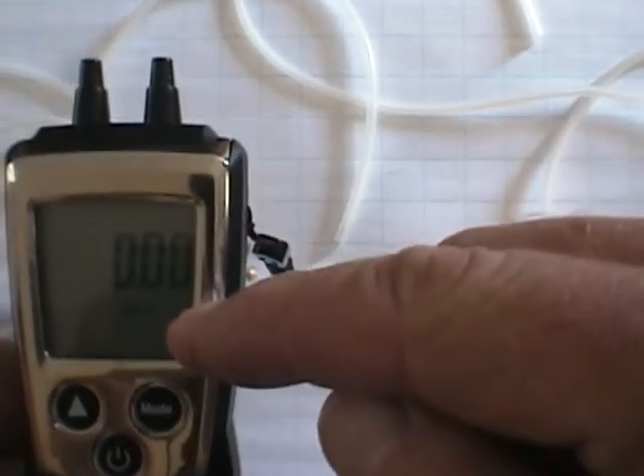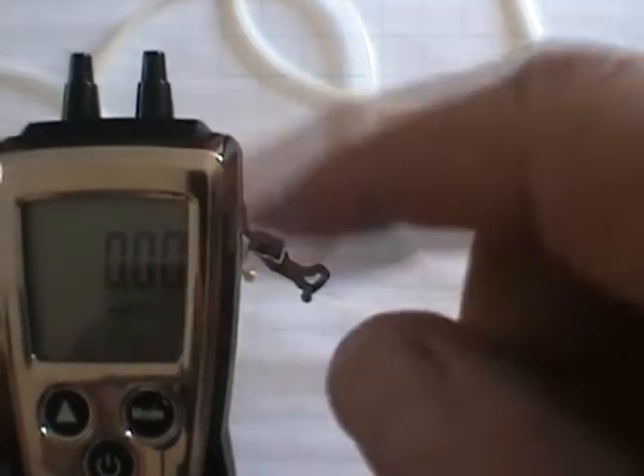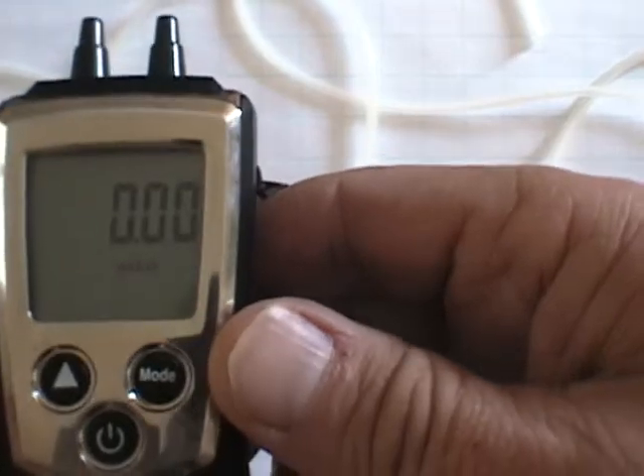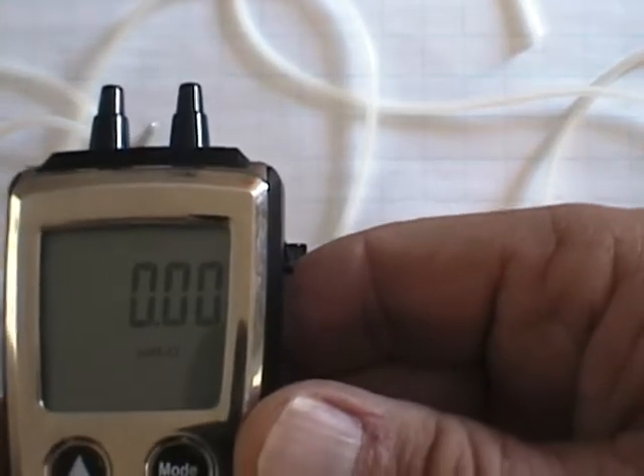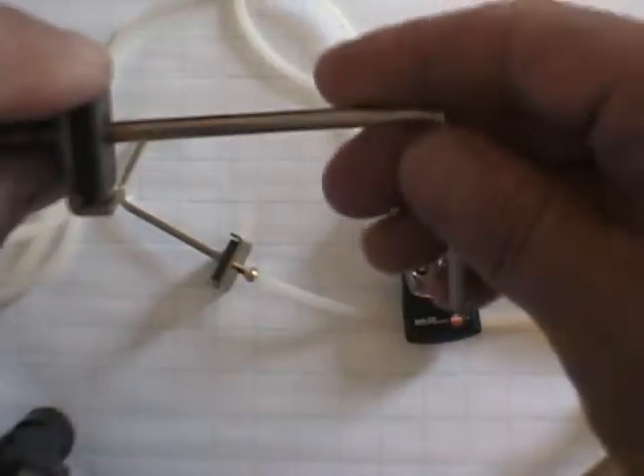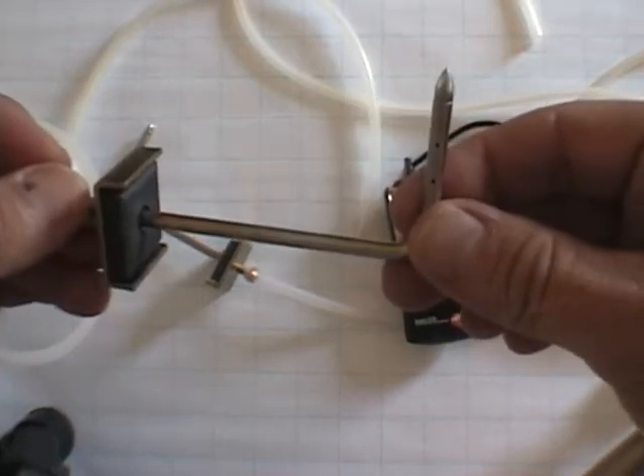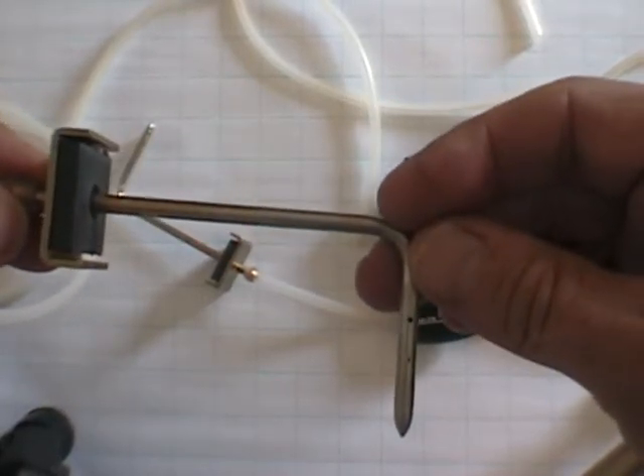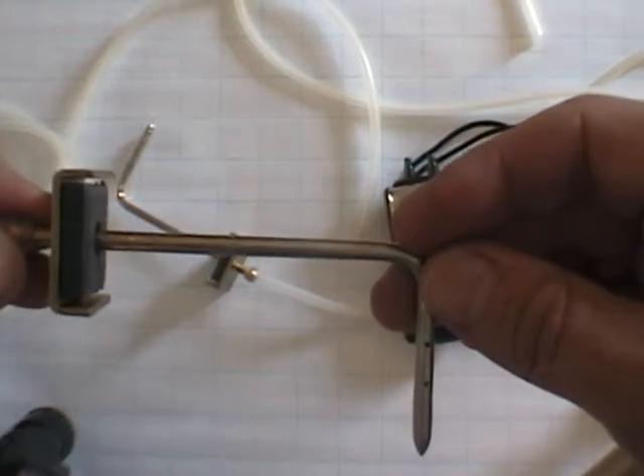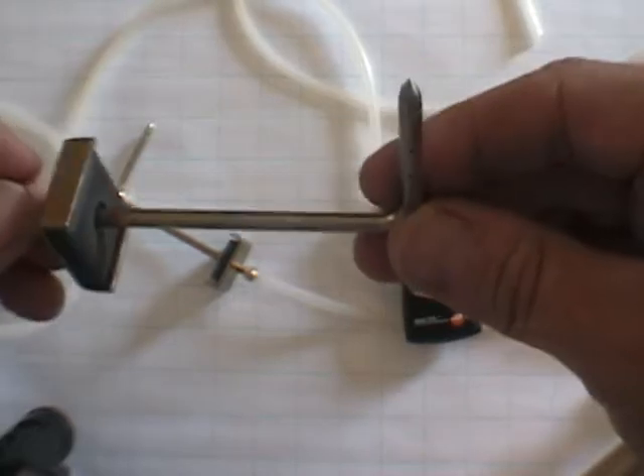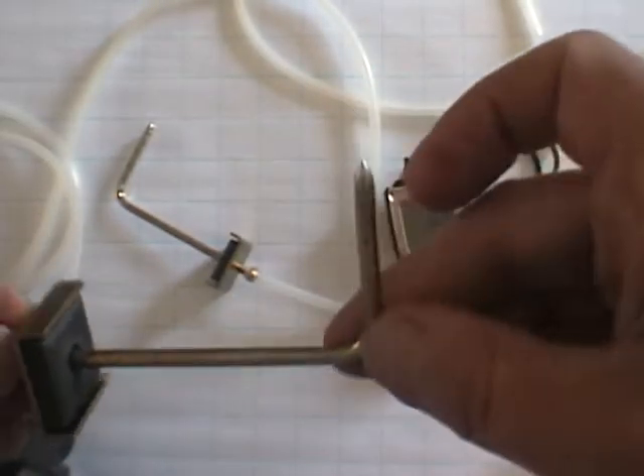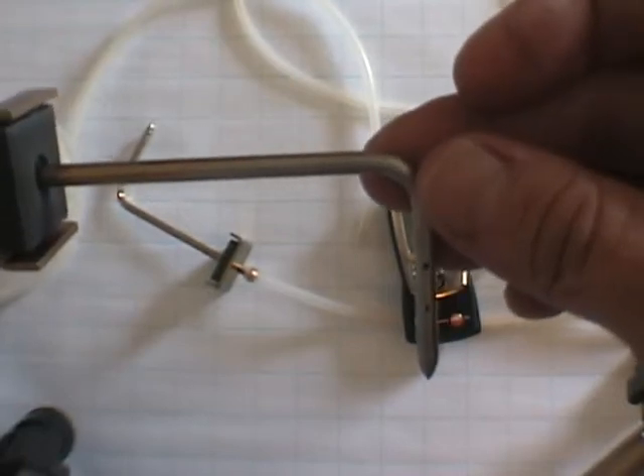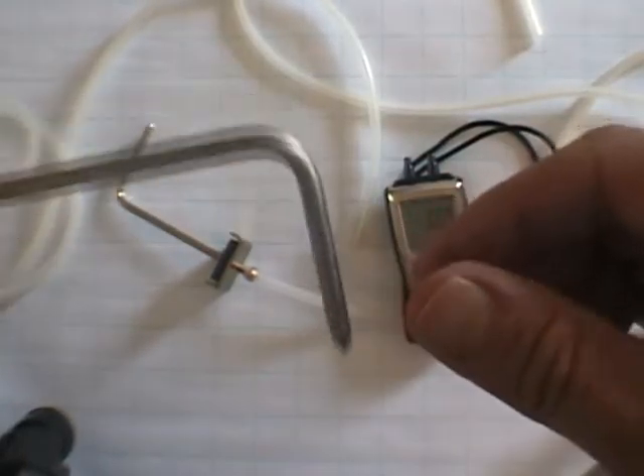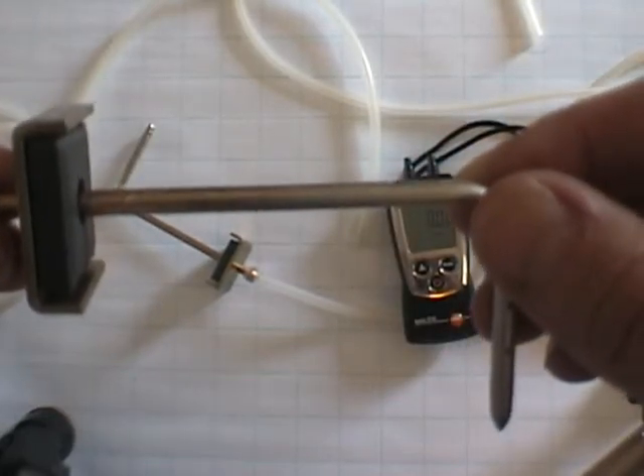So it's zeroed out. The unit of measure we're using is inches H2O. You can change it to PA and multiple other units of measure, but we typically use inches of H2O. So when we take the measurement, we're going to place the pressure probe into the unit in the suction side of the fan and in the discharge airstream, either before or after the component that we want to measure. This is not a pitot tube. There's no hole in the end. There are holes in the side. So this installs in the airstream with the point here facing into the direction of the airflow.